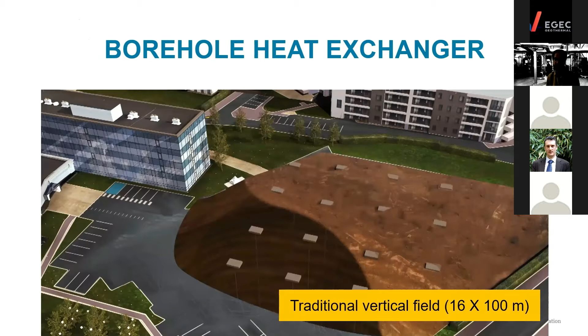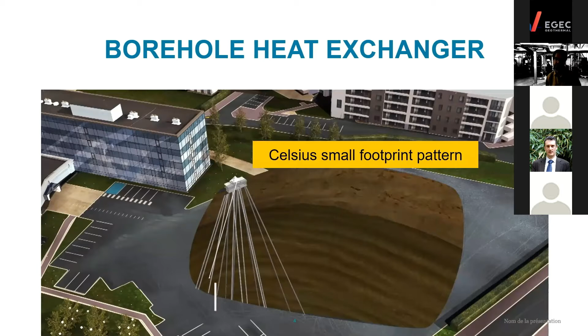Instead, the decision was to use a radial pattern where deviated probes radiate outside from a single small footprint wellhead, thus obtaining a smaller occupation of the soil at surface during the drilling. So the building of the borehole heat exchanger was done while the building was occupied and the parking was in use. And at the surface, we only have a small site to mark the location of the wellhead nearer to the building. So the idea is that this can be done while a building is used.